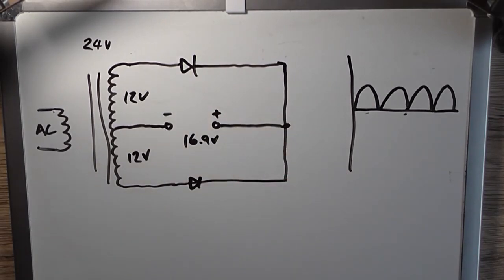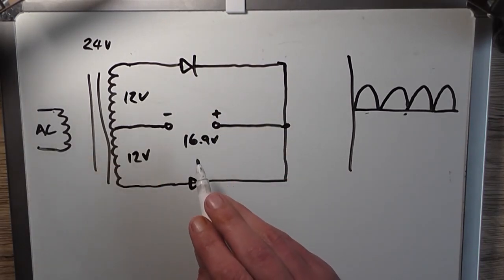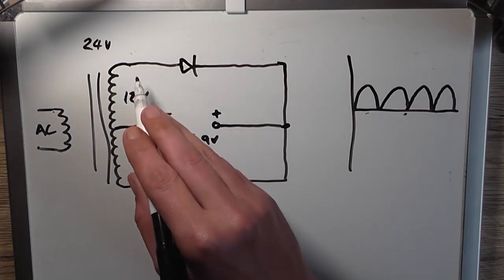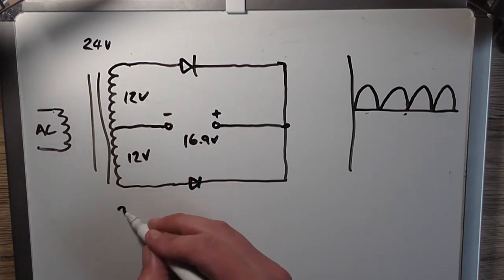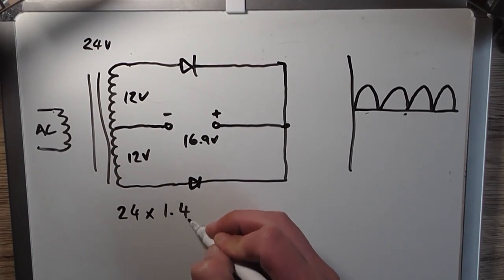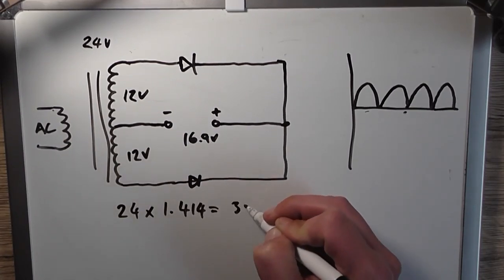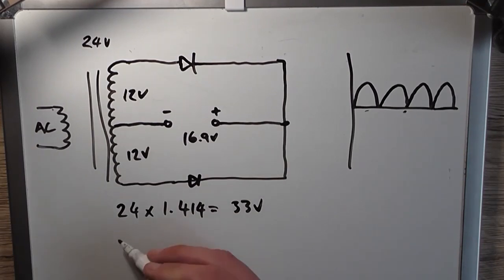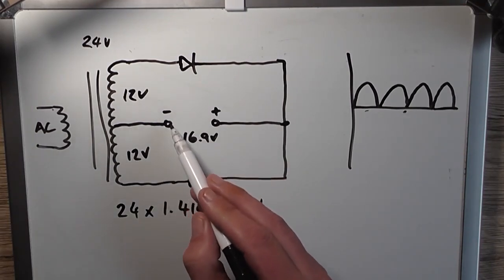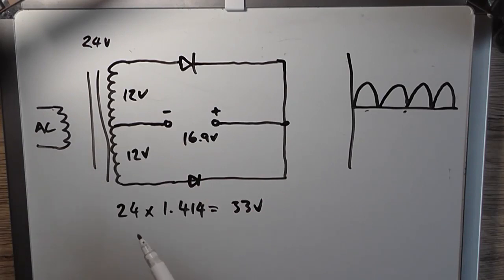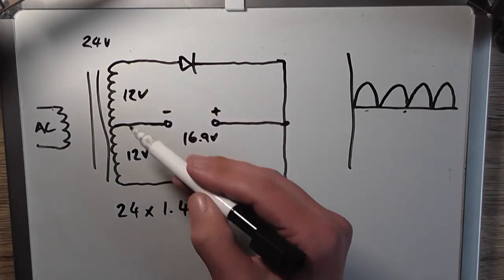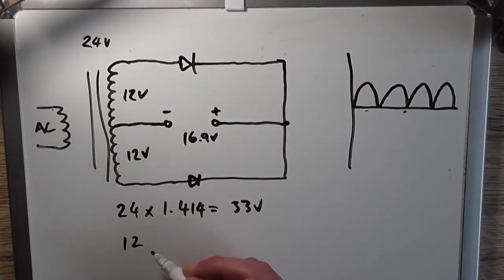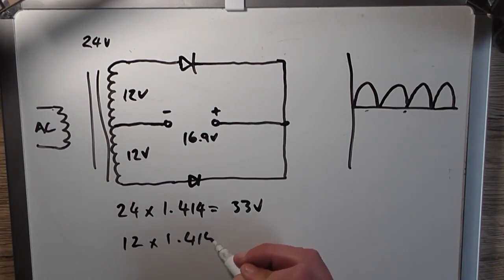That's it - not anywhere near like 32 volt, which you would kind of expect if you were to go 24 times 1.414, which would equal around about 33 volt. Because this negative is now referenced to the center tap, that means it's only ever going to be half potential. So that actually will be 12 times 1.414, which equals 16.9 volt, and that's all we're ever going to get.